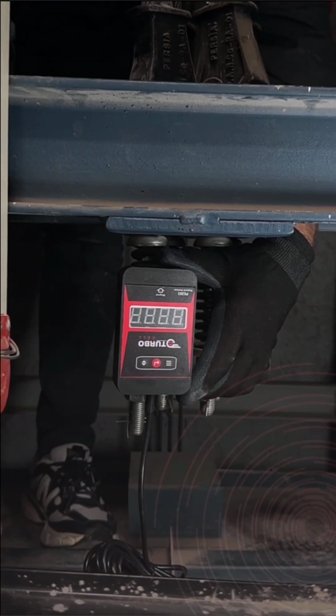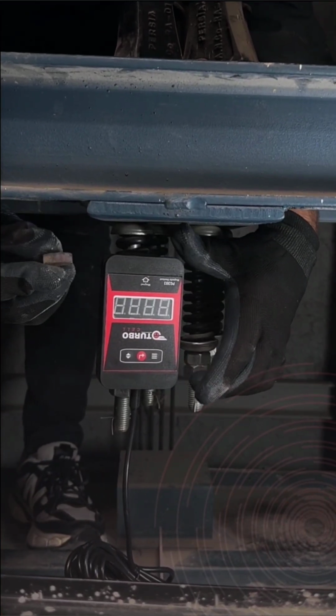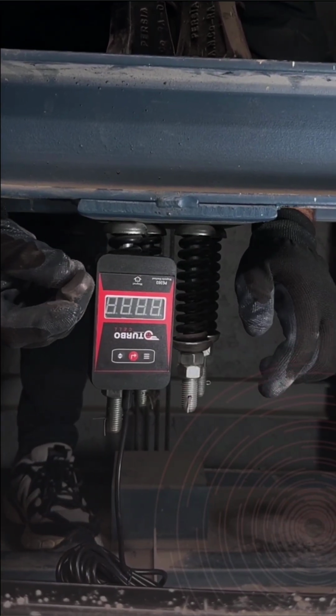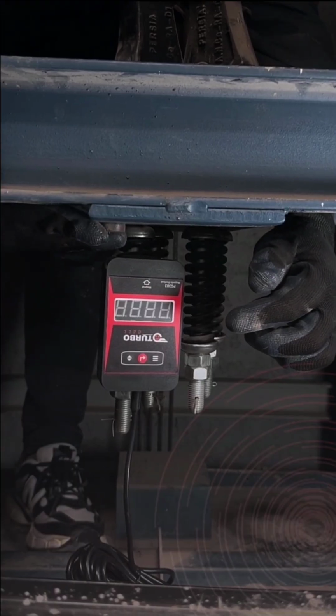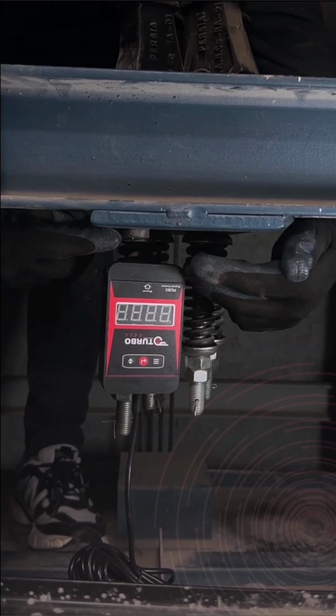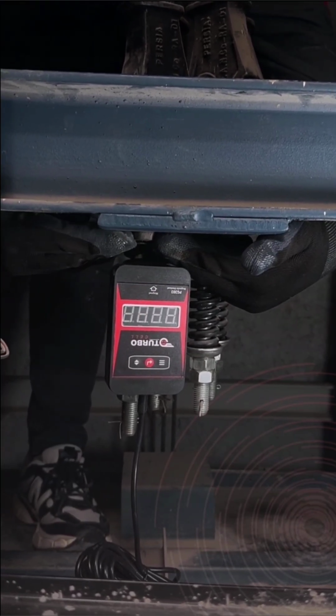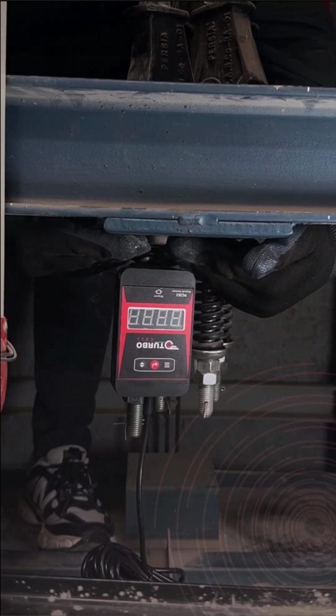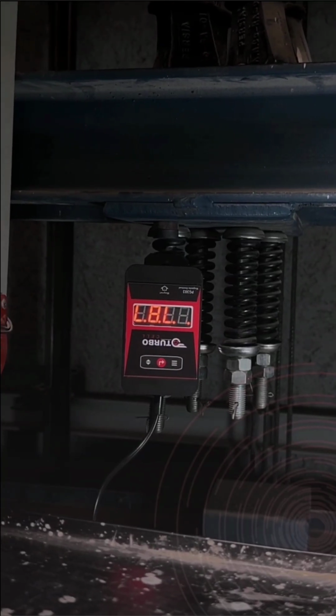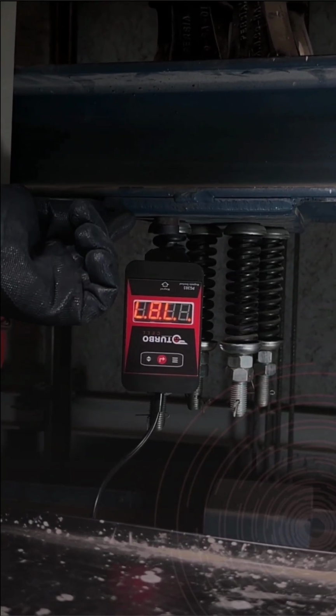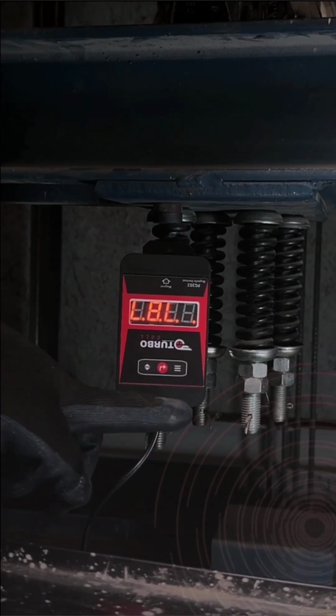Reverse installation, inverted mounting on cabin. If the device is installed in reverse, the magnet must still be aligned with the arrow marked on the unit. In this case, the displayed values may appear inverted. To fix this, hold the menu button (3-line icon) for 3 seconds to enter the configuration menu.